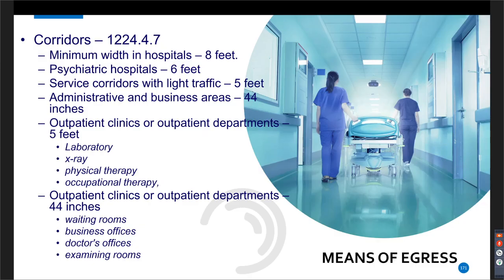And then some specifics for the corridor width. So again, you've got requirements in chapter 10, and then you have some specifics in chapter 12. There are some allowances to reduce, depending on your situation, the width of the corridors. So the minimum width for hospitals is 8 feet. But if it's a psych hospital and they're ambulatory, they can go to 6 feet. Service corridors with light traffic can go to 5 feet. The admin and business areas can be 44 inches. Outpatient clinics or outpatient departments could have 5 feet. And then some examples there, the lab, x-ray, physical therapy, and occupational therapy go down to that.